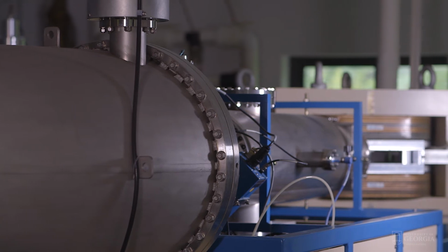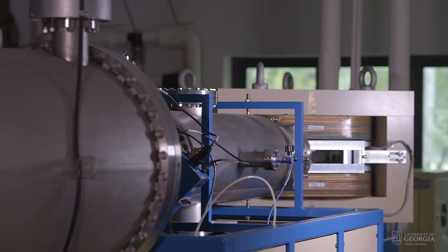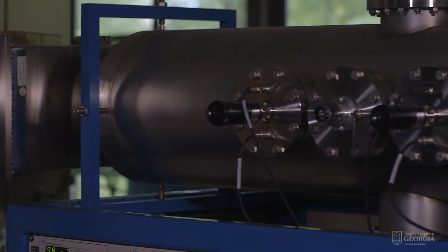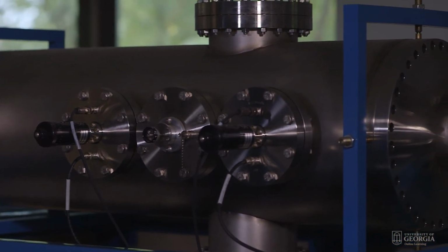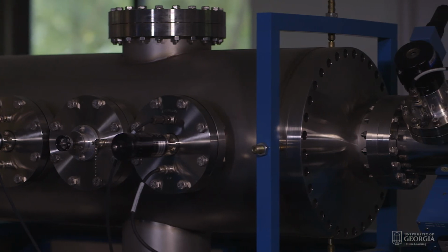Once it goes through that magnet, it goes through the center chamber of the accelerator. That's actually the accelerator, where it gives a whole lot of energy to those ions. And it also pushes it through what we call a stripper gas, which reverses the polarity. So before we had negative ions, now we have positive ions that are going to be pulled towards another electromagnet. Once again, it'll go through that electromagnetic field. It'll refine those beams of carbon ions based on their mass to charge ratio.